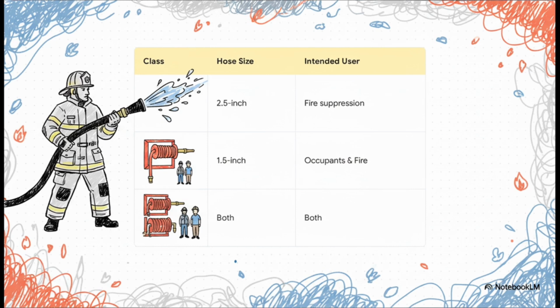Class 2 systems, which are sometimes referred to as house lines, provide a smaller 1.5-inch hose and a nozzle that are actually stored right there on a rack. These are designed for use by either trained building occupants or fire personnel to attack smaller, incipient fires before they spread. And finally, a Class 3 system is the best of both worlds. It combines the features of both, offering the small hose station for occupants alongside that massive 2.5-inch connection for the heavy fire streams used by the pros.